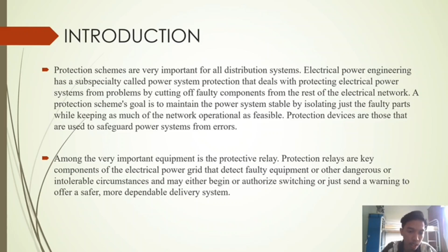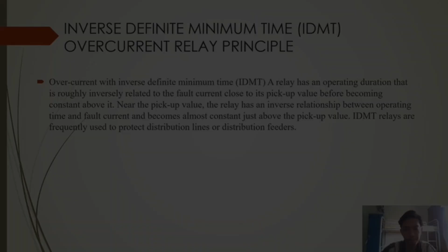So we chose the inverse definite minimum time, IDMT, overcurrent relay as our group project. This is the principle of an overcurrent relay with inverse definite minimum time, IDMT. A relay has an operation duration that is roughly inversely related to the fault current close to its pickup value before becoming constant above it. Near the pickup value, the relay has an inverse relationship between operating time and fault current, and becomes almost constant just above the pickup value. IDMT relays are frequently used to protect distribution lines or distribution feeders. That's all from me. Thank you.